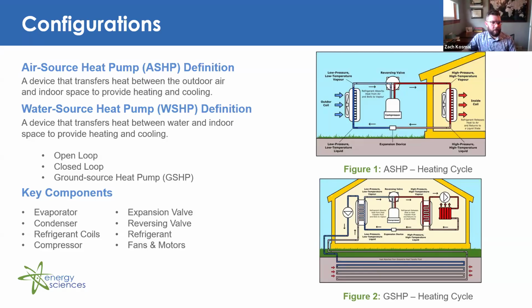In general, heat pump systems can be utilized across many industries and applications to transfer heat for the purpose of heating, cooling, and waste heat recovery. But typically their system components remain the same. So we have the key components listed here. You have your evaporator and condenser, your refrigerant coils, compressor, expansion valve, reversing valve, refrigerant, and your fans and motors.